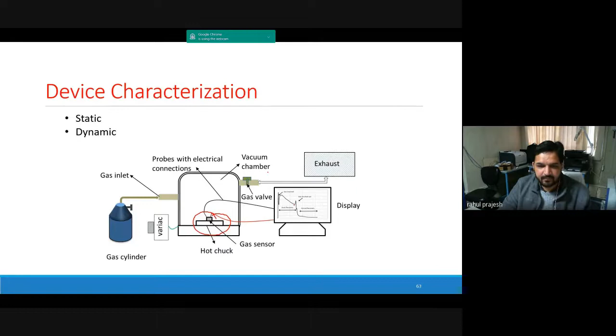So this is a complete setup where you see the chamber where you put the sensor. This sensor is driven by one supply for the micro heater and another for measurement of the sensing film resistance. This is the computerized system where you have different MFCs. At times we can use 4 MFCs in this system. So 2 MFCs, one is for the target gas, one is for oxygen, air. You mix different proportions of the gas to make different ppm concentrations, and you push that into the chamber, and the chamber is connected with the supplies and meters. This is the schematic of the same setup where you have this chamber. The device is connected to the monitor as well as the supplies. You have a cylinder which goes inside the chamber.